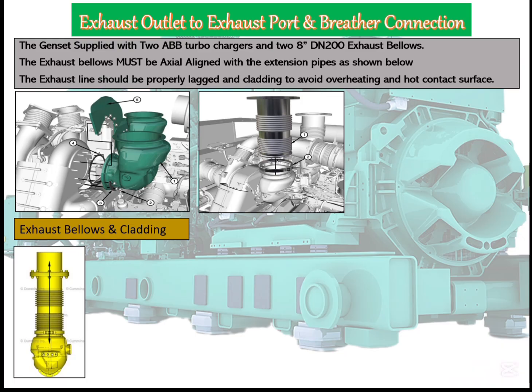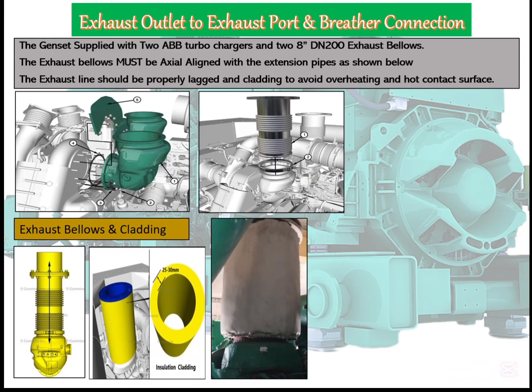Here are some pictures of exhaust. In the first picture, we can see two turbochargers connected with an elbow to the exhaust outlet points. In the second picture, we have exhaust bellows. In the third one, I mentioned that it should be axially aligned. Whenever we use these bellows, they should be clad so that the hot surface will not radiate heat around that area. So we have harness and other cables that are not burnt off.